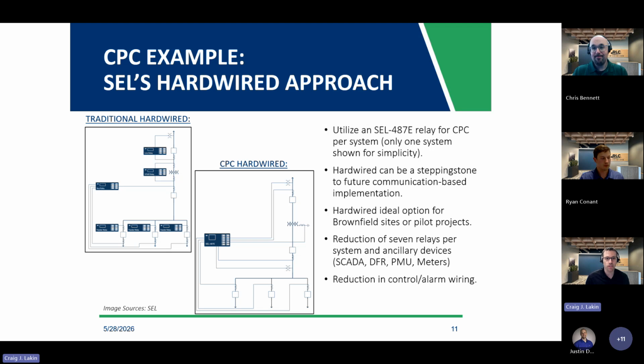In this example, basically, instead of having a bunch of distributed relays, we are now going to have one centralized relay that will perform the same functions as the decentralized relays. So driving right into it, in our left example here, the traditional hardwired design would have basically 6 relays in this example, and we'd be consolidating down to 1 relay. All of the functions would still exist. They would just be implemented in software in 1 device instead of in 6 separate devices.